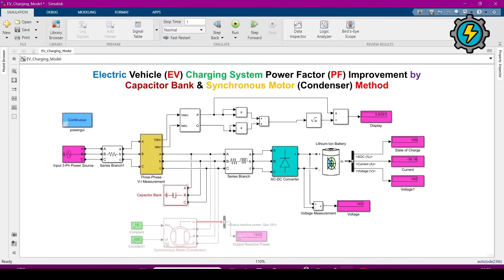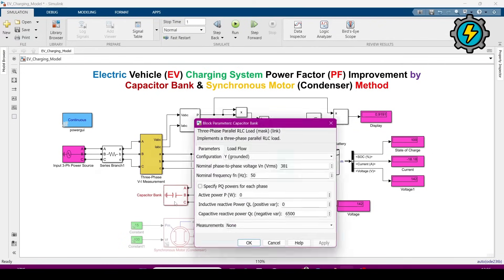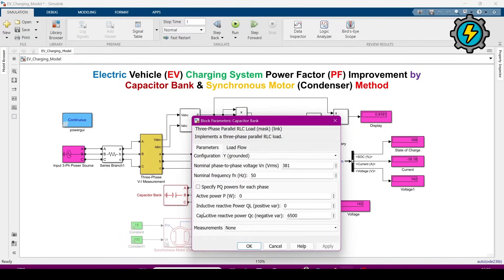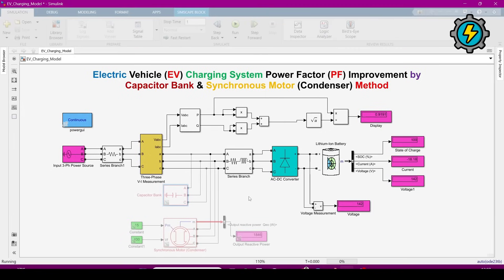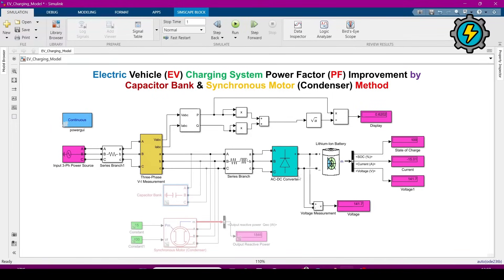We can see the output reactive power by double-clicking on the capacitor bank. This shows the reactive power supplied by the capacitor bank, the RMS voltage, and the frequency. The power factor is now improved. I will again comment out this block and run the simulation — it goes back to 0.62. Now I will attach the synchronous condenser block.